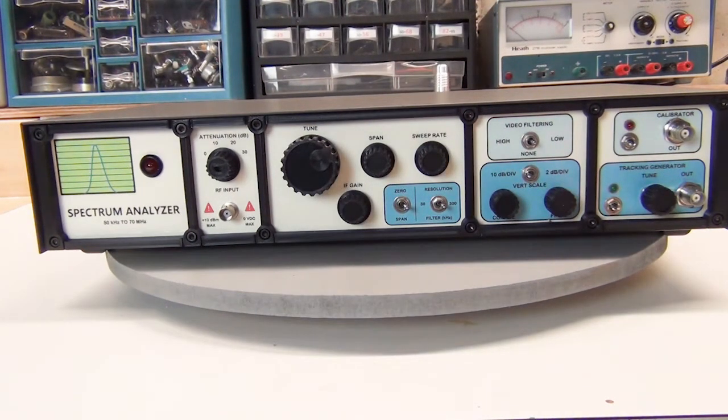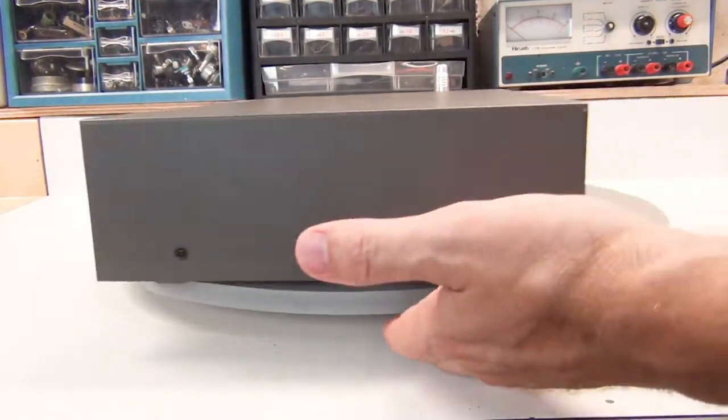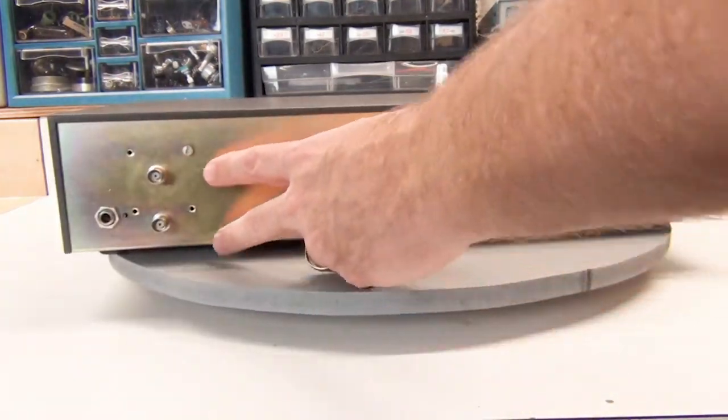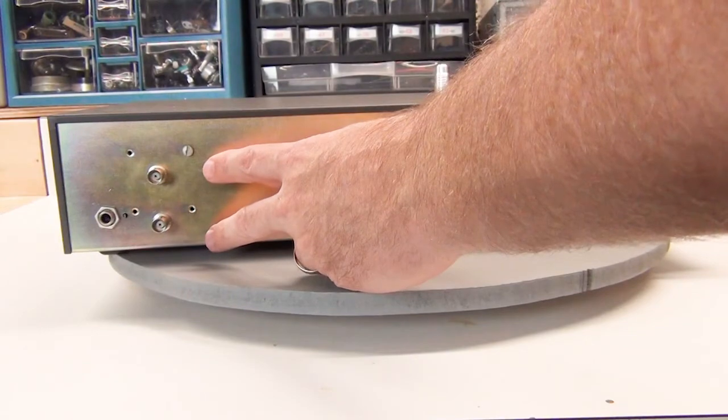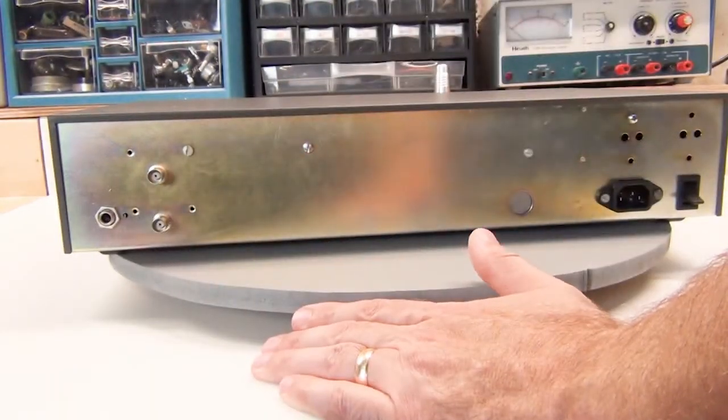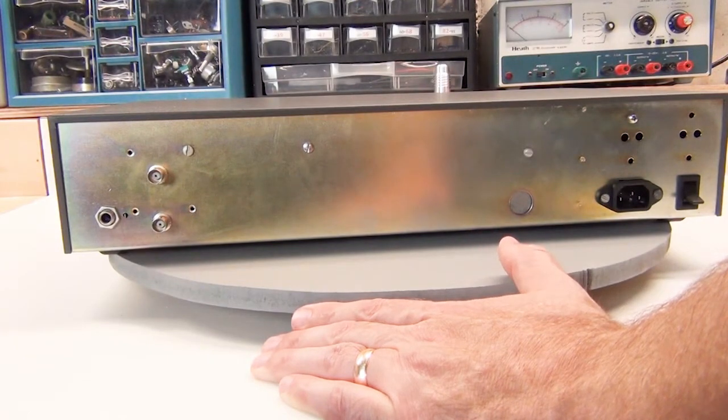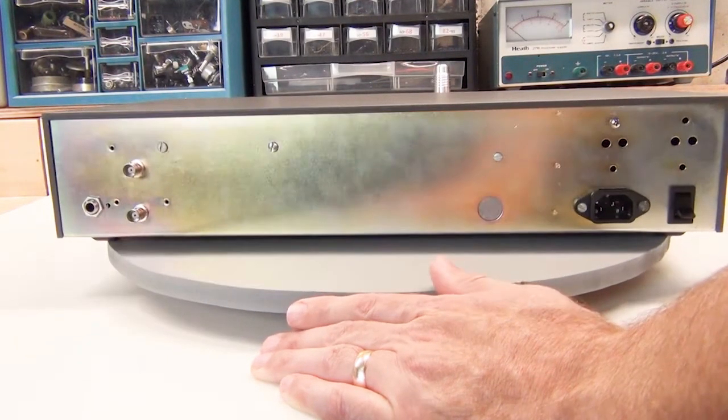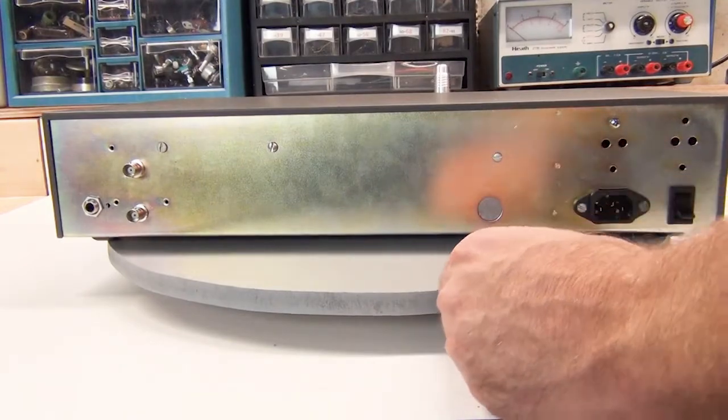I'll spin the turntable around at this point so we can take a look at the back. And it is pretty simple. There's just two BNC connectors here, one for x-axis and y-axis to connect to the oscilloscope. There's a potentiometer there that is adjusted during calibration to set the final gain of the amplifier. And then of course power and power switch.